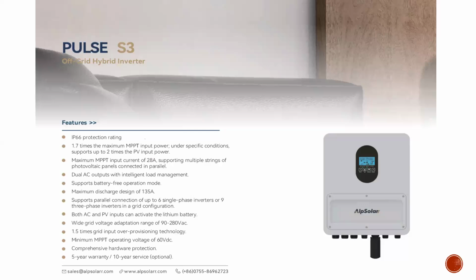Yeah, of course, that leads me to the next unique selling point, which is that it has 1.5 times grid input over-provisioning technology, right? What this is saying in essence is that this inverter can take more power from the grid than its rated capacity. Though it's a 6 kilowatt inverter, it can take up to about 8 or 9 kilowatts from the grid, and it will take it easily without damage to the components of the inverter. So you can take more power from the grid to charge your battery and supply your load at the same time.